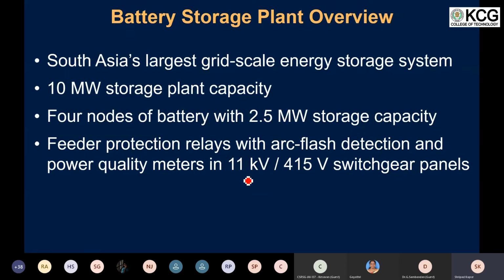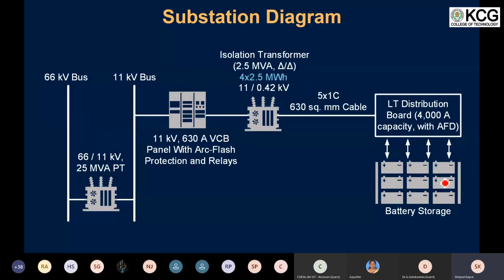If you look at this particular substation, we have the battery storage units, and from the battery storage units, using the inverters, they are connected to the 415 volt switchboard level. From the 415 volt switchboard level, the voltage is stepped up to 11 kV, and then from 11 kV it is again stepped up to 33 kV to be connected to the grid. This is also a typical scheme that you may find in any renewable integration. When we look at solar photovoltaic based generation, you would have a similar kind of approach. You may have batteries in some cases, or in some cases the photovoltaic cells directly connected to the 415 volt switchboard and then stepped up to a voltage level which is suitable for the substation to be connected.